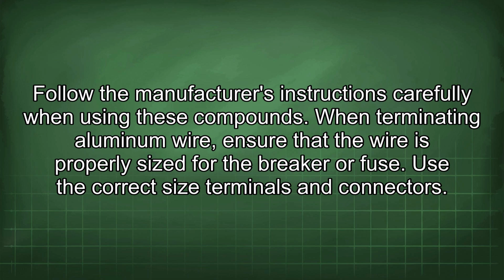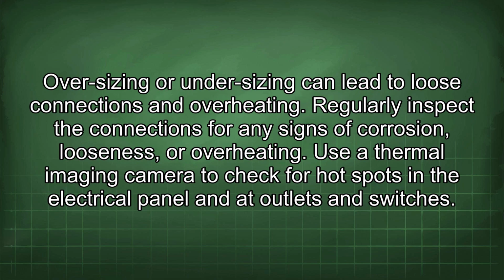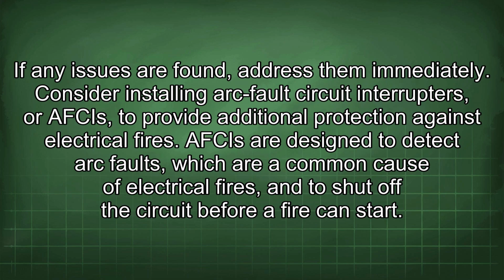When terminating aluminum wire, ensure that the wire is properly sized for the breaker or fuse. Use the correct size terminals and connectors. Oversizing or undersizing can lead to loose connections and overheating. Regularly inspect the connections for any signs of corrosion, looseness, or overheating. Use a thermal imaging camera to check for hot spots in the electrical panel and at outlets and switches. If any issues are found, address them immediately.